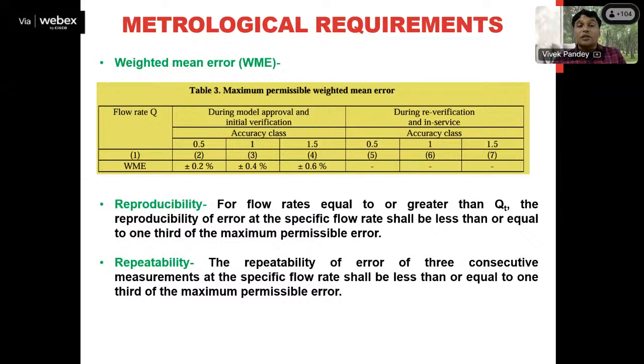Similarly, when we are doing the reproducibility test, what is it? It is a little bit the same as repeatability, but there is one difference: whenever we are performing the reproducibility test, the flow rate might change. We can change the flow rate. Suppose I take the same example of the gas flow meter where the minimum flow rate is 100 liter per hour and the maximum flow rate is 500 liter per hour. Suppose we take the first reading at 100 liter per hour, the second reading at 200 liter per hour, and the third reading at 400 liter per hour. But we are transferring the same quantity of gas during all these transactions or tests.